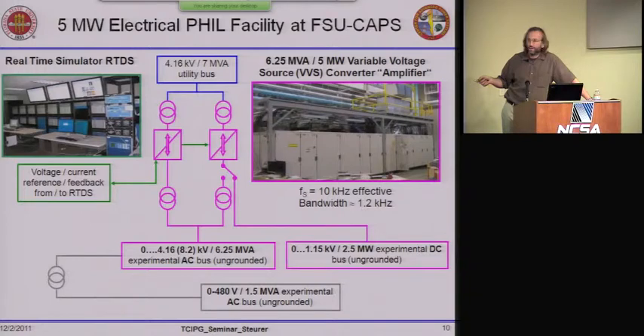Now, and you will see at a later slide, you can actually connect a power device between those two buses. For example, a photovoltaic inverter that on the one hand believes it's connected to a photovoltaic array, and on the other side it's connected to a 480 volt utility bus, yet the device is completely isolated from a real PV array or from a real utility bus because we are simulating both sides. Okay, so that's the idea. This device essentially acts as an amplifier to the signals that come out of the real-time simulator. Did that answer your question?